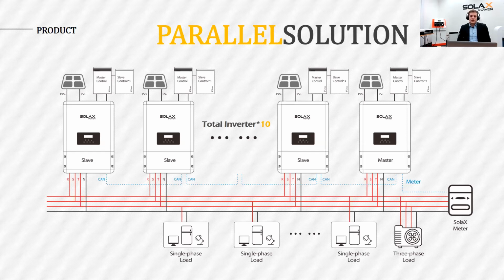The big plus of this: in balanced mode, if you need 5 kilowatts on one phase but can only give out 3, you have to buy 2 kilowatts from the grid, for example when cooking. But with unbalanced mode, it can provide every demand needed and you don't have to buy any energy from the grid, as long as the system is big enough to supply your house.